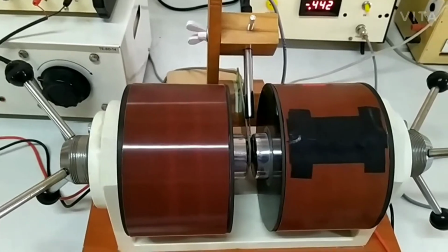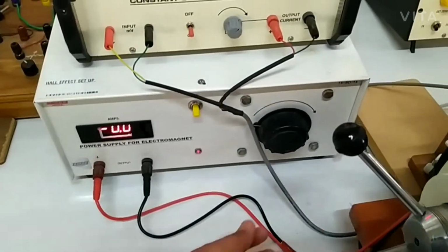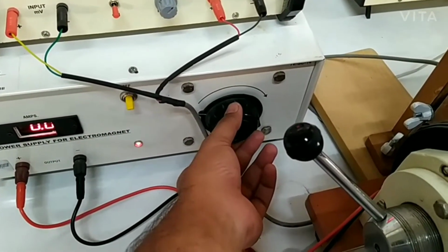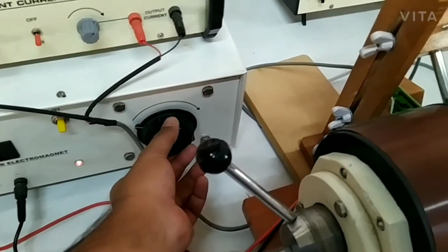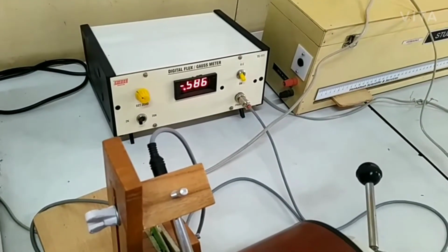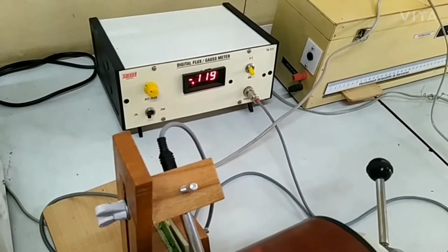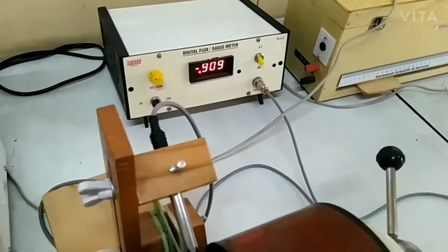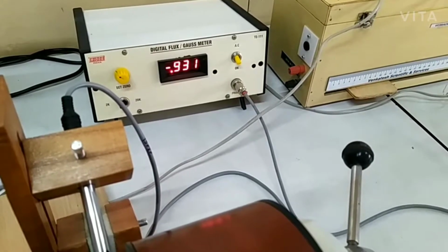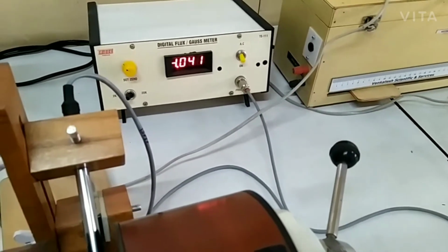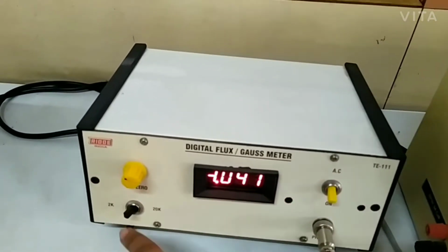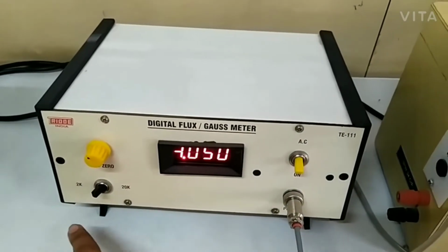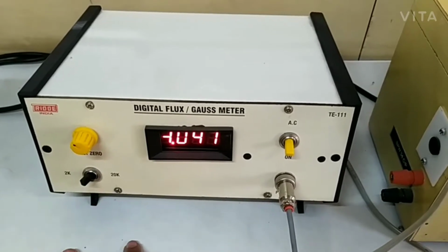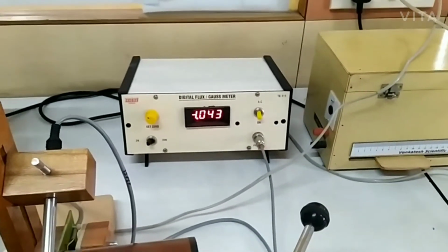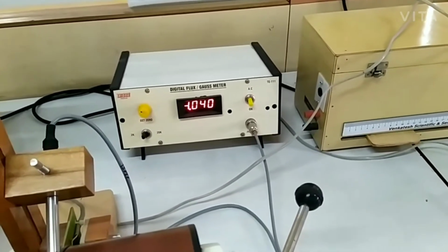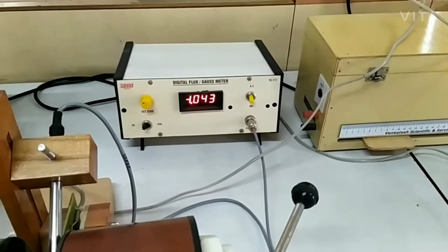To adjust the magnetic field in these coils, we will adjust the current in it. While rotating this knob, rotate it slowly and observe the magnetic field measured by the Gauss probe. Adjust this to 1 kilogauss. We can see here there are knobs. This shows 2K, this shows 20K. That means the maximum range for this knob is 2K. If we switch it to this side, the maximum range will be 20K. So right now it is 1 point something. That means it is 1 kilogauss, which is equal to 0.1 Tesla.